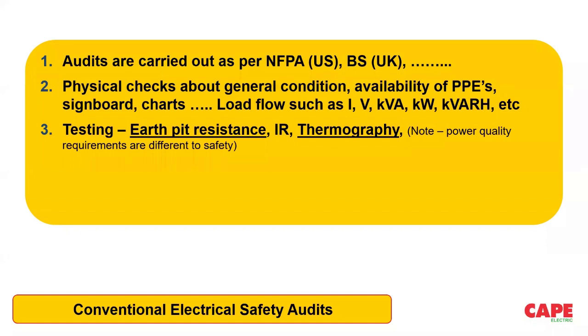In almost all the electrical safety audits, testings are carried out. I have put 3 testings which are generally carried out in this case. Not all the 3 are generally carried out. The first one, earth pit resistance, the resistance measurement of the earth electrode, is always carried out. The second one, IR, insulation resistance, is not done very carefully, but sometimes the IR measurements are done, and thermography. In modern buildings, thermography is done because people believe that by making a thermography, you can achieve safety, which is absolutely not 100% correct.